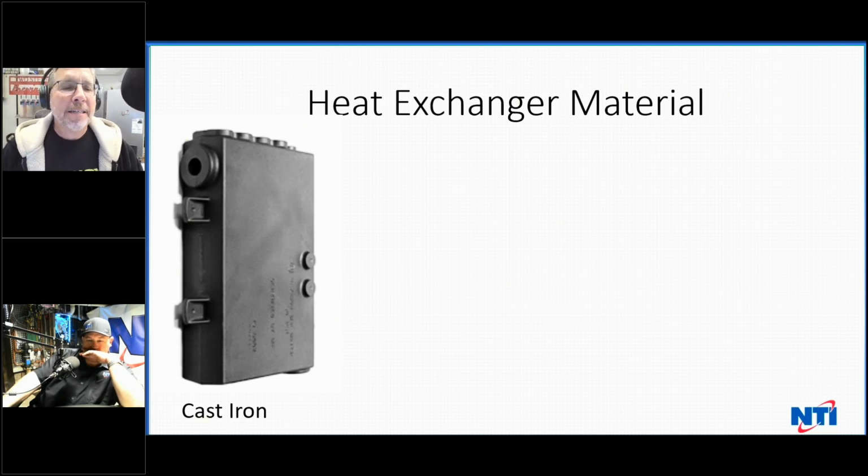Oh, okay, thanks. Greg Super says here in PA, a lot of townships are requiring you to do load calculations. So too in New Jersey and New York, Greg. That's not just us. If you're getting inspected, most inspectors want to see a load calculation because they know if the boiler is 3 times the size it needs to be, it's only running at 30% of its rated efficiency, which is horrible. But anyway, let's go on and look at some heat exchangers that are on the market.